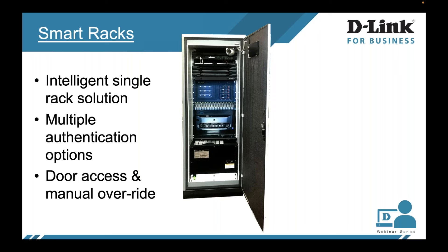The moment you set this threshold and the temperature goes beyond 22 degrees, locally the text on your screen changes from white to red to draw attention of the person sitting there. Remotely, it will trigger an SMS or email alert so the IT manager knows there is a problem. He can then direct the on-site person to visit and resolve the issue. With temperature and humidity sensors, you always know what is happening inside. UPS provides backup for power failures based on your requirement.